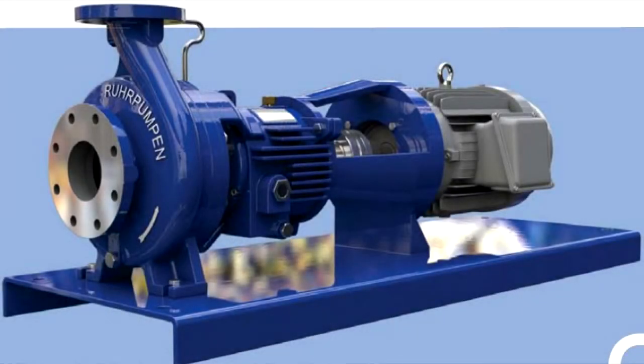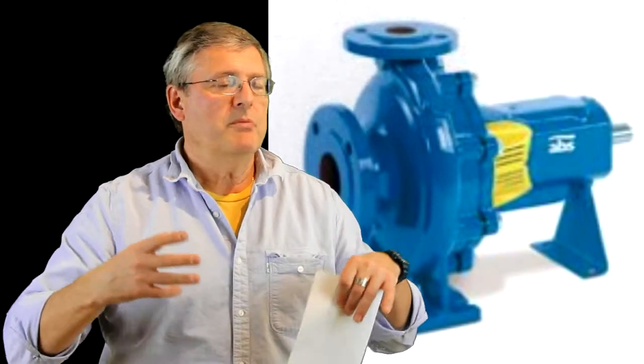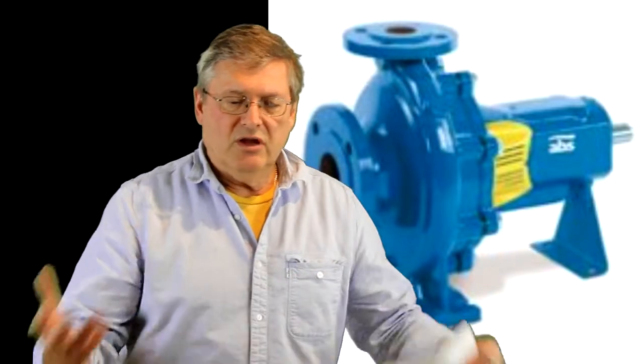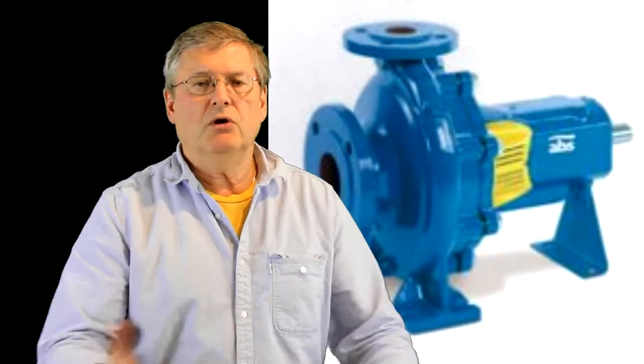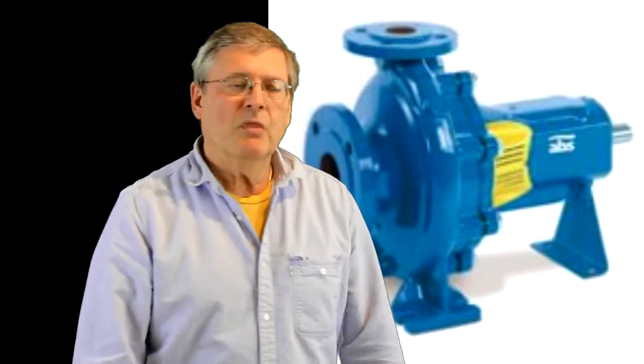This next pump is the typical centrifugal volute type pump. This is the workhorse of the industry. This pump you see everywhere in just about every industry imaginable. It comes in different sizes, of course, very large range of flow and pressure, comes in different materials. If you have corrosive materials, aggressive materials, even very aggressive slurries, you use a similar type of pump like this except they'll have a liner inside, and the materials of the pump and impeller can be in Teflon and all kinds of polyethylene types of materials for aggressive liquids. This is really the workhorse of the industry.